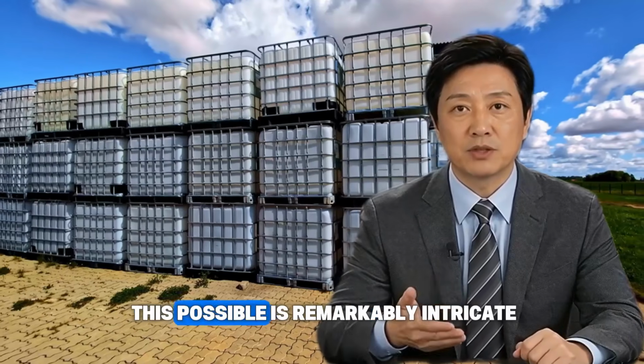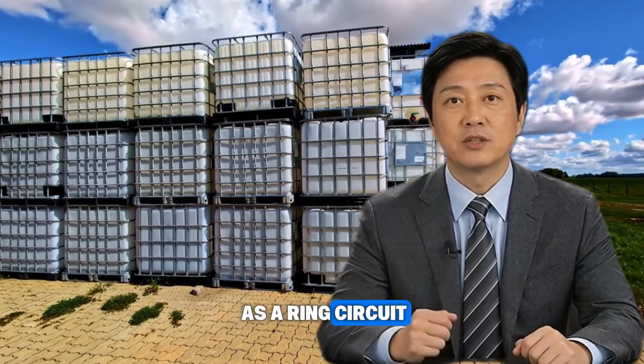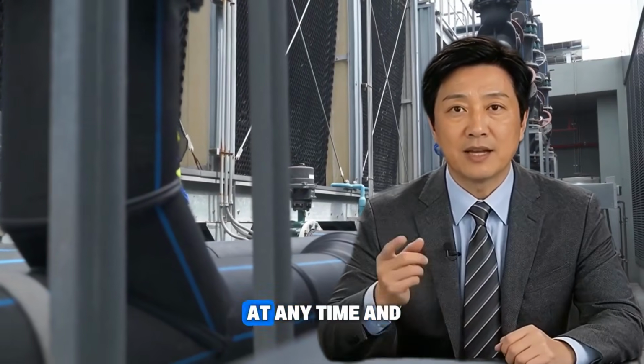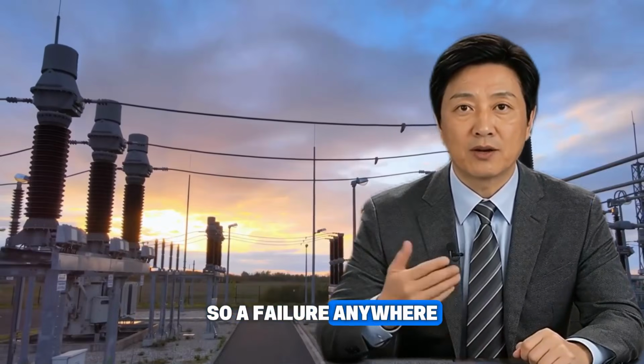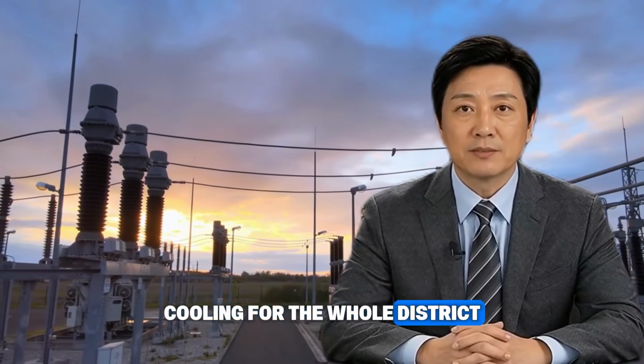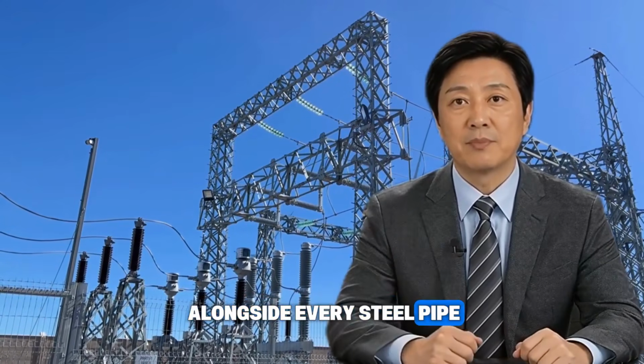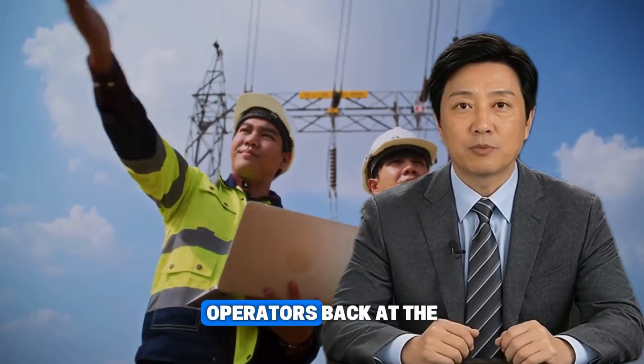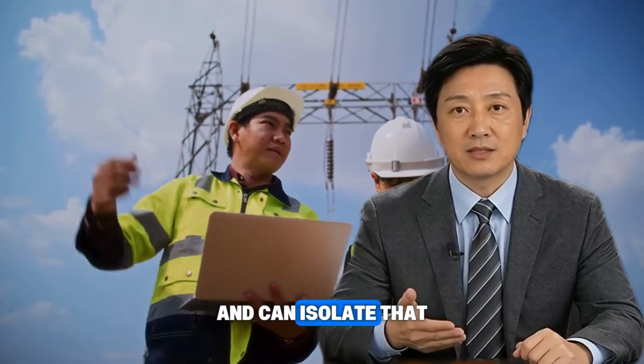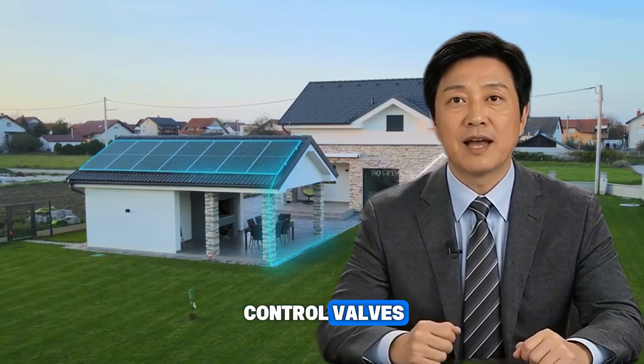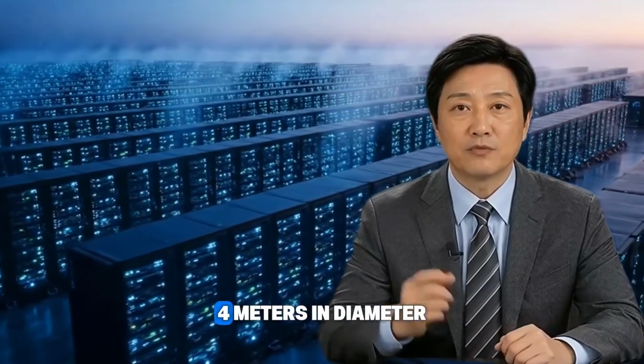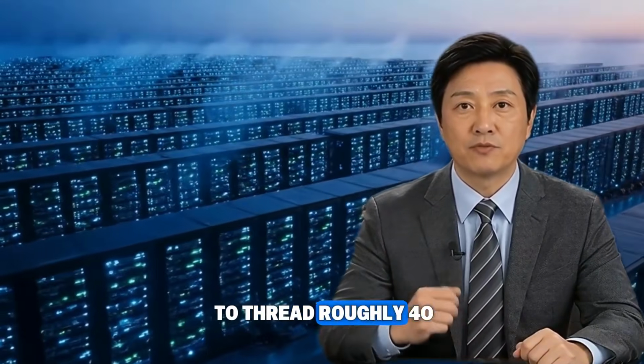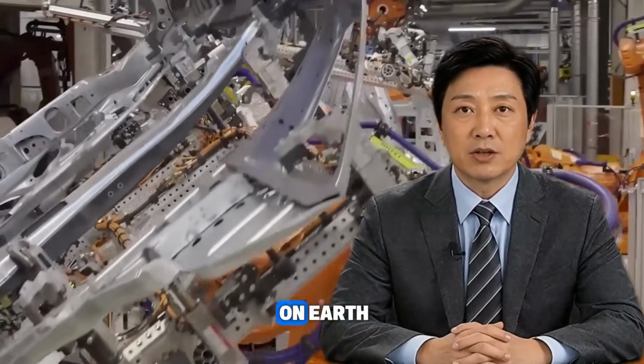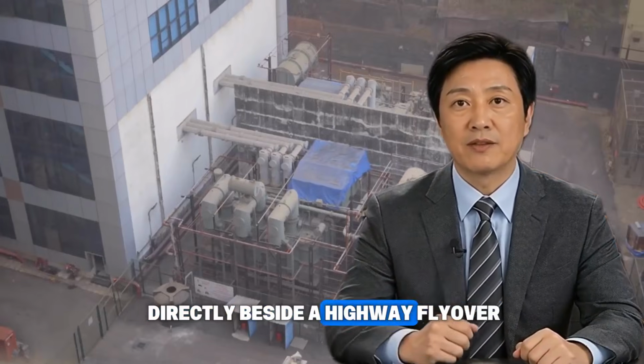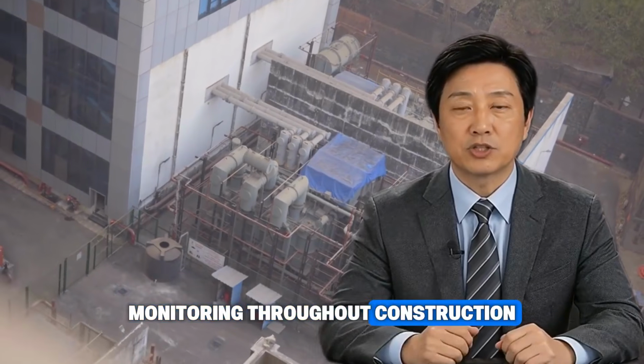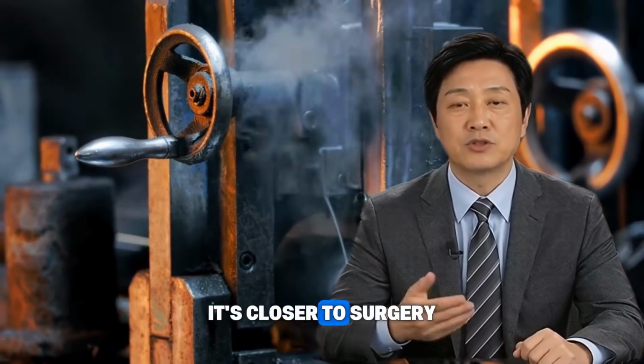The engineering that makes this possible is remarkably intricate. The network is built as a ring circuit using a 3-pipe interlink system, with 2 pipes active at any time and 1 held in reserve, so a failure anywhere in the system doesn't shut down cooling for the whole district. Leak detection cables run alongside every steel pipe, so if water ever escapes anywhere in the network, operators back at the plant see the signal immediately and can isolate that exact section using remote control valves. The pipes themselves range from 1 to 1.4 meters in diameter, and construction crews had to thread roughly 40 kilometers of them through one of the most congested urban sites on Earth, at one point digging directly beside a highway flyover that needed constant movement monitoring throughout construction. This isn't ordinary plumbing. It's closer to surgery performed on a city.